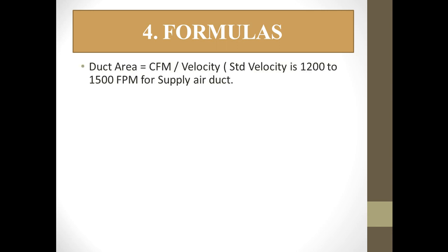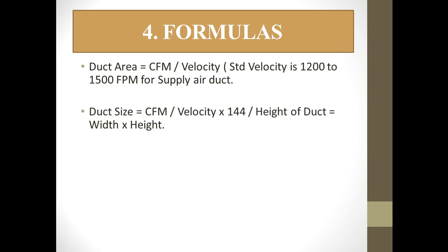Now let us come to the formulas — the 4th section. These formulas are required for ducting and air distribution products. To calculate duct area: Duct Area = CFM / Velocity, where the standard velocity is 1200 to 1500 FPM for supply air duct. To calculate duct size: Duct Size = CFM / (Velocity × 144), where 144 converts to square inches. Divide the result by the duct height to get the width, giving you width × height dimensions.